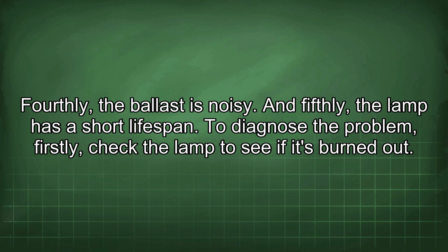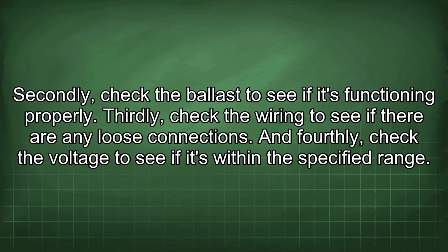To diagnose the problem, firstly, check the lamp to see if it's burned out. Secondly, check the ballast to see if it's functioning properly. Thirdly, check the wiring to see if there are any loose connections. And fourthly, check the voltage to see if it's within the specified range.